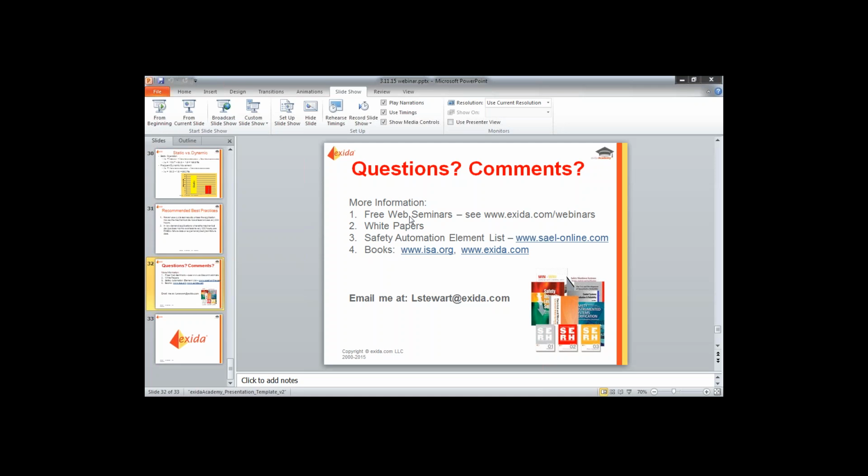And then the next part of the question, how does the exida database cater for different services, clean versus plugging? The component database we use actually has different services. So you have a clean service or a severe service environment, and unless it's stated that you're selling your valve only for clean conditions, we give out clean and severe services. Also, we have different environments. We look at if this would be an offshore application. We look at if this is going to be an application indoors, which has a pretty clean environment. We look at if this application is going to be deep sea or have a lot of corrosion capabilities. So we look at all of the services, and we cater each FMEDA to the way each product is going to be used.